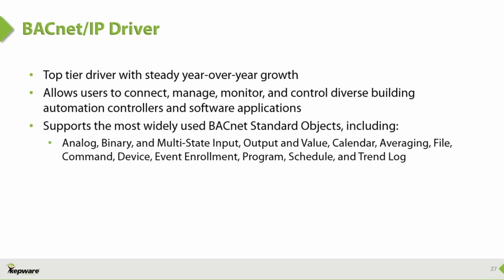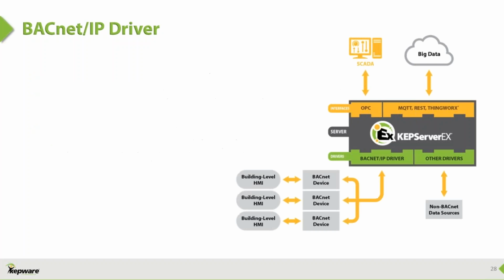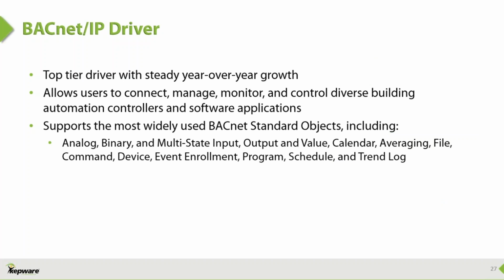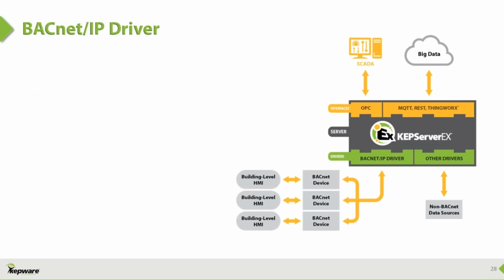Because BACnet uses an object-oriented model for abstracting and representing information, the approach includes a list of standard objects covering many common and generally useful applications. Kepware currently supports most of the more commonly used standard objects, including analog, binary, multi-state input, output and value, calendar, averaging, file, command, device, event enrollment, program, schedule, and trend log.